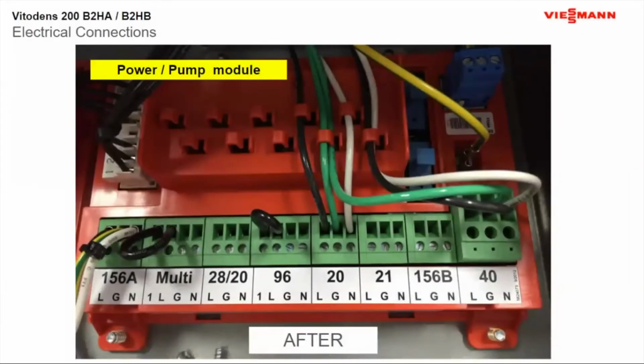So now you can see how the wires actually go. And for years, I was always wondering what these little loops were, but that's how you wire in your wire. Just hold it, it makes it look neater. But your 40 plug is going to be your incoming power, and that 20 pump, remember, is going to be that pump underneath the boiler to activate your flow switch. That's always going to be on your 20 pump.